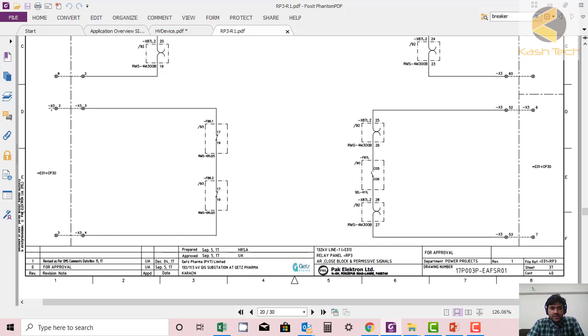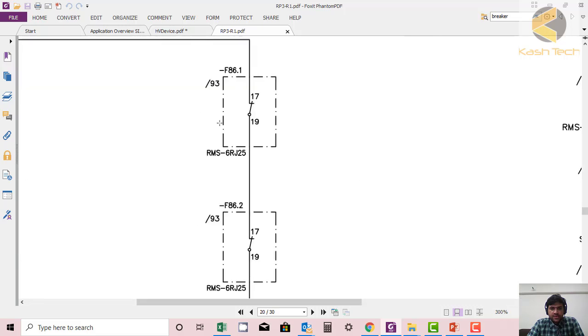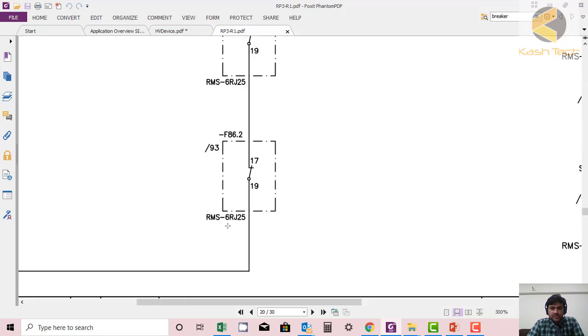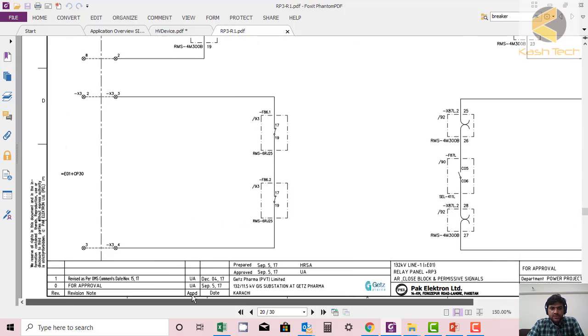Here it's coming from the LCC and then it's passing through lockout F86.1 in series with another lockout 6.2, and then again it's going back to the control panel. It means that this DC supply should be through each lockout relay contact, NC contact. So any contact operate, it should be able to block the closing.